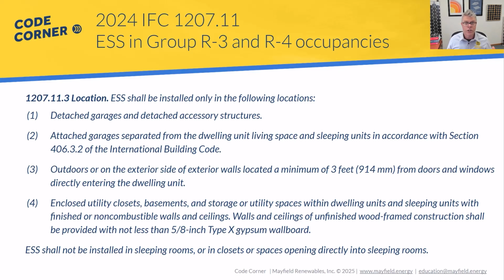So there are actually some requirements for that door, and fire ratings on the door, how it's constructed, that it is self-closing, self-latching. So that's one that you should be aware of if you're putting these inside of a garage. That entry door into the dwelling unit may also need to get replaced because of these requirements.